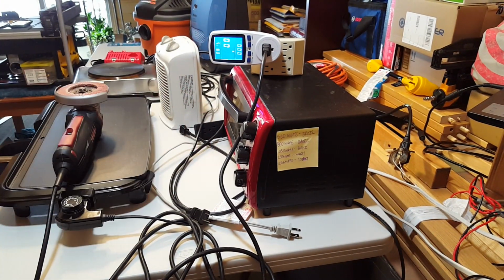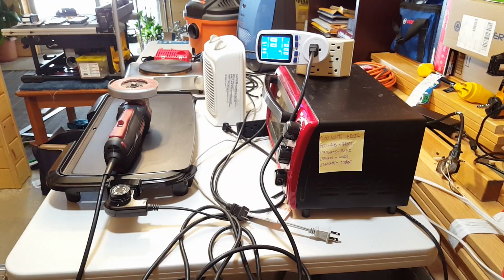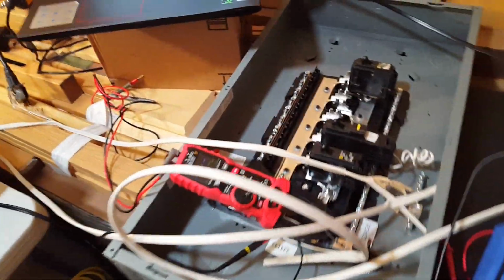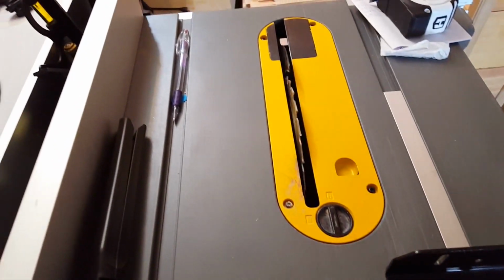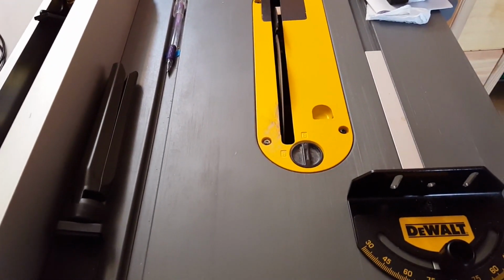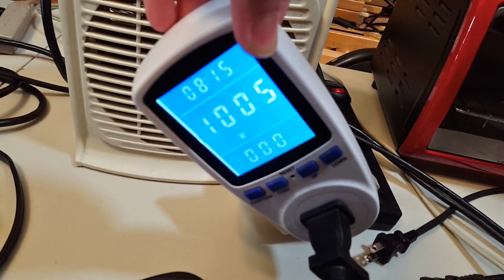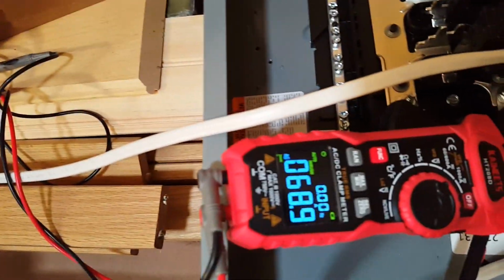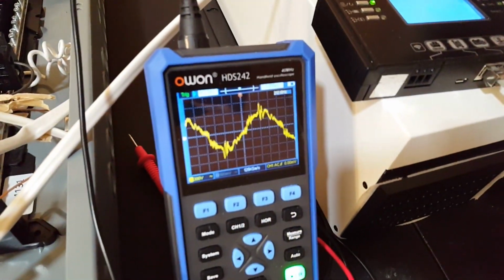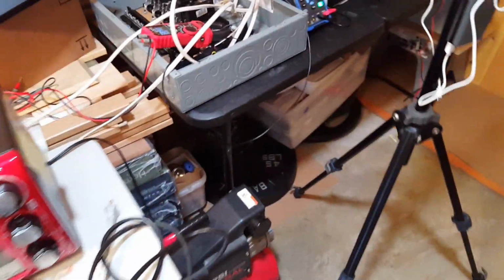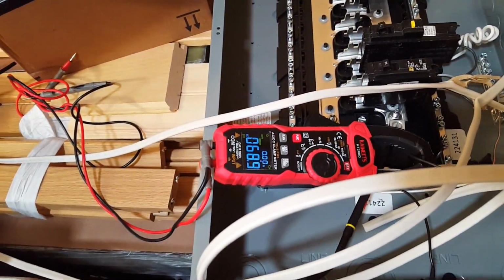A single load. That's gonna be the table saw. We're gonna check AC amps in. We're just gonna start with checking inrush on bypass mode. Ready to start. Bypass mode surge test. Here we go. It draws 1,000 watts on the surge amp. 68.9. Here's the AC waveform. 68.9 amps surge on grid.